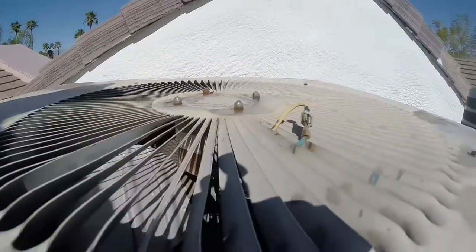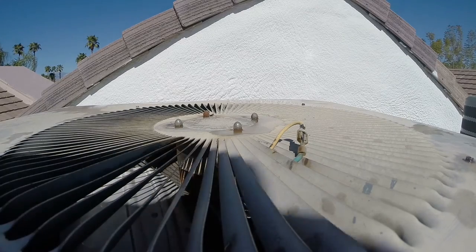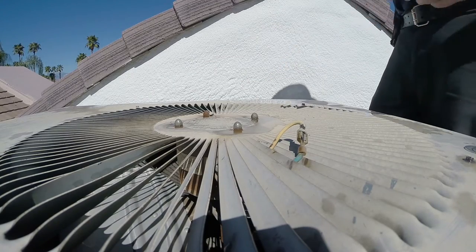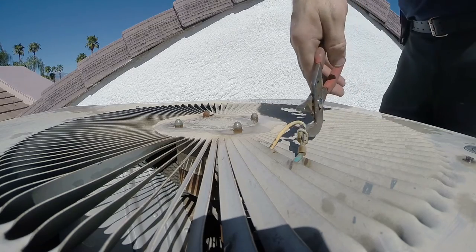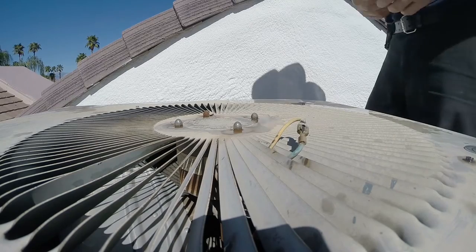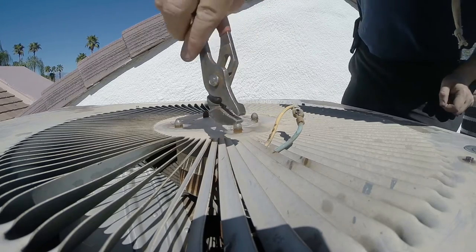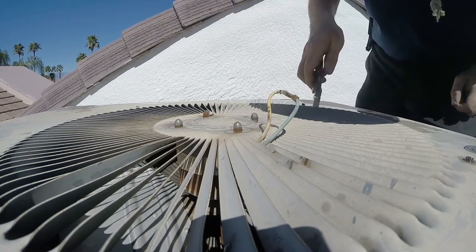Just a little more preventative maintenance. I got a lid here that's cracking pretty good. What I got is some fender washers just to preserve things. It's maybe time to replace the unit here and there. I do what I can to keep it alive. And look, this is hanging down and actually getting pretty close to that fan motor as well.